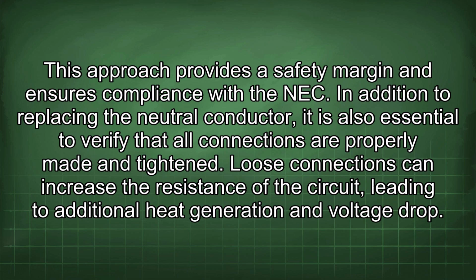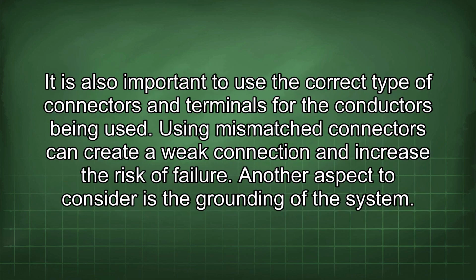In addition to replacing the neutral conductor, it is also essential to verify that all connections are properly made and tightened. Loose connections can increase the resistance of the circuit, leading to additional heat generation and voltage drop. It is also important to use the correct type of connectors and terminals for the conductors being used. Using mismatched connectors can create a weak connection and increase the risk of failure.